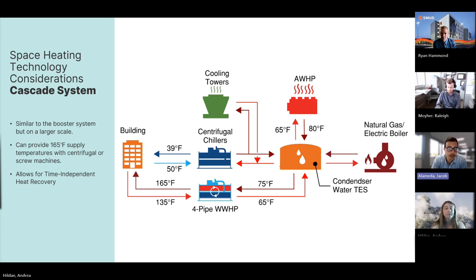For example, we're looking at a campus right now that has 23 buildings on it, and all of them are set up for 180-degree heating water. So changing out the coils and the piping in all of those buildings to accommodate 130-degree heating water could be a serious challenge. Not to mention just the increased size of the distribution piping that would be needed to get water to those buildings.